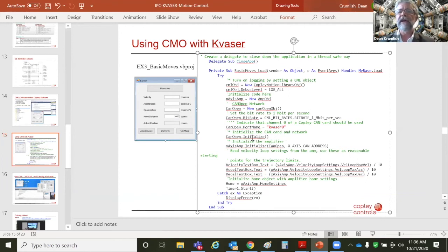You initialize a CAN network. You could initialize 2 networks because you have a 2-channel card, CAN 1 and CAN 2. You could put all your drives over here, and that's 2 times 127 nodes on 2 networks. And you can talk to them, so you can do multiple networks from the software.